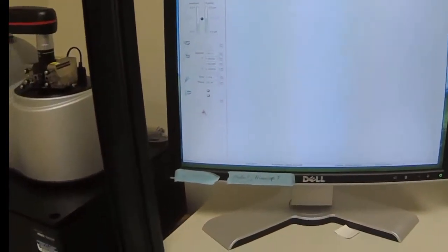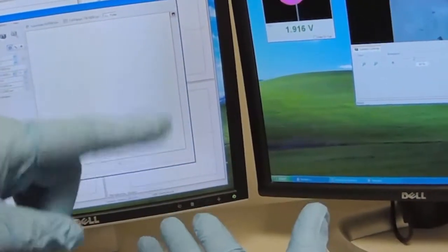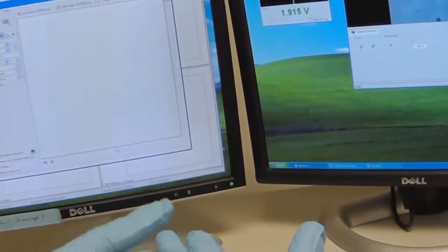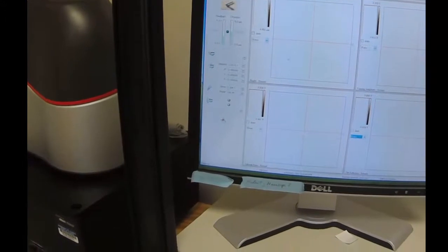This is the position of the scanner crystal going up and down, raising and lowering the sample, getting it close to that cantilever. What it's looking for is when it reaches this set point, this voltage, which has to do with the amplitude of the vibration of the cantilever. When it starts tapping the surface, that will dampen that amplitude to reach a certain set point. Every time it does this cycle, the motors also move it a little bit closer each time until we reach the set point.